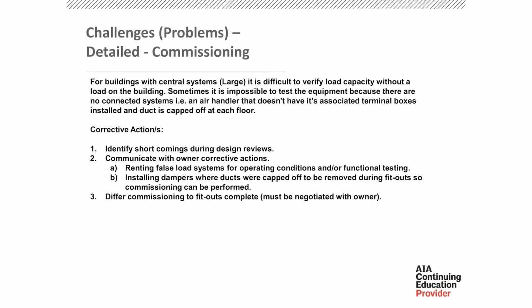Ensure the building and fit out balancers provide reports for the commission agent to review. So you have to have the documentation for when the next balancer or somebody else comes through. For buildings with a central large area, it is difficult to verify the load capacity without load from the building. Sometimes it's impossible to test the equipment because there are no connected systems. So that goes back to the dark shells: an air handler that does not have the associated terminal boxes installed, and the duct is capped off for each floor.